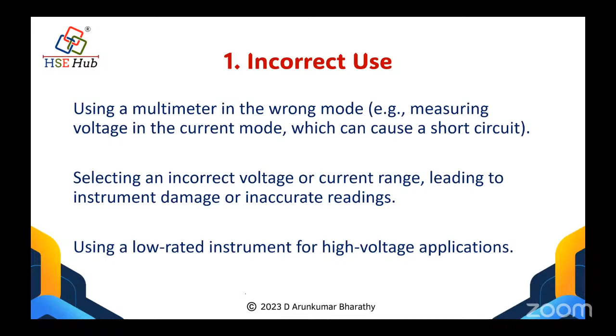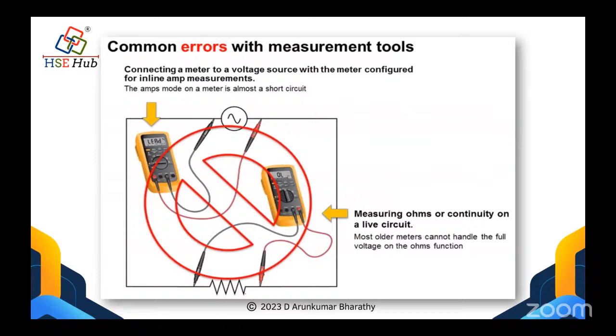You can see this common error, where they don't change the selector and finally the instrument burns out. If it's a good quality instrument, it will just blow the fuse. But if it's a wrong, unrated, or poor quality damaged equipment, it can cause a shock to the user.